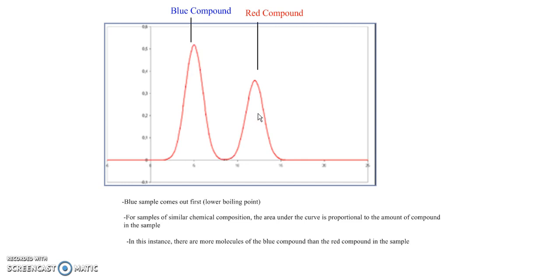So maybe a slower gas flow rate will help the peaks separate more, but the peaks in that case will be a little broader. These are things that are adjusted and played around with when you're trying to optimize the separation of the peaks.